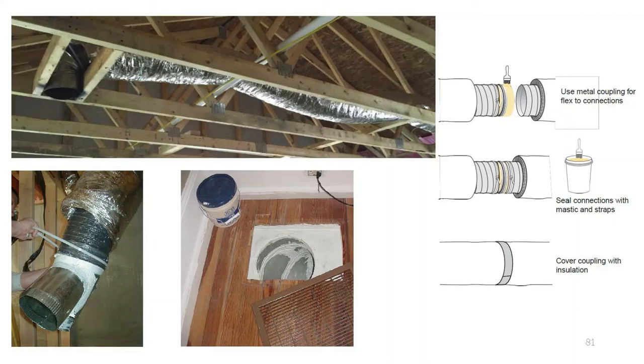Another common leak location in all ducts is the point where the duct boot connects to the drywall or subfloor. The final image in this set shows mastic sealing at the boot. Notice how thick the mastic is applied in these images. You want it to be as thick as a nickel. If there's tape beneath the mastic, you don't want to be able to read the writing on the tape.